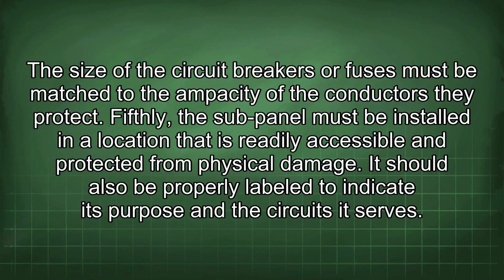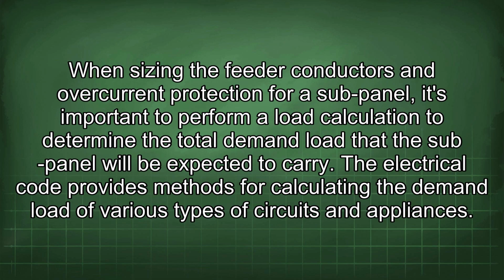Fifthly, the sub-panel must be installed in a location that is readily accessible and protected from physical damage. It should also be properly labeled to indicate its purpose and the circuits it serves. When sizing the feeder conductors and overcurrent protection for a sub-panel, it's important to perform a load calculation to determine the total demand load that the sub-panel will be expected to carry. The electrical code provides methods for calculating the demand load of various types of circuits and appliances.